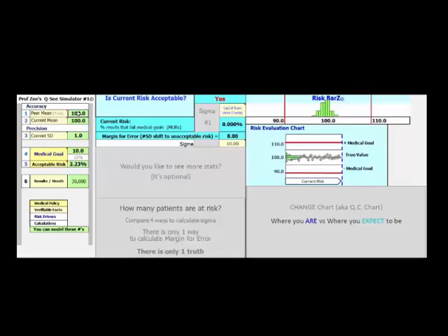If the peer mean was 98 instead, then this would be a positive bias. If the peer mean was actually 95, this would be a stronger positive bias. But if the peer mean was 106, then we have a negative bias. It's the relationship between the peer mean and the current mean that determines accuracy and bias. I'm putting this back to 100.